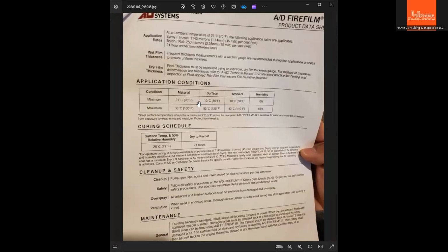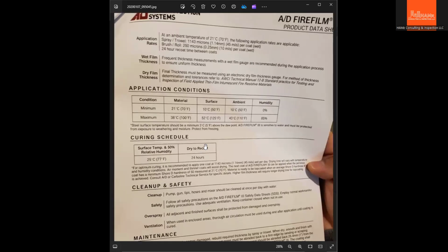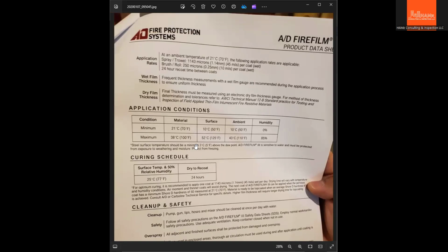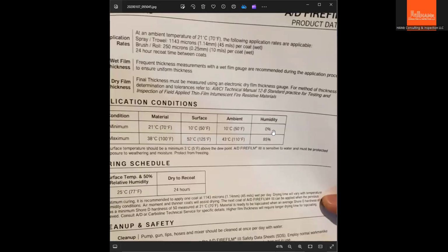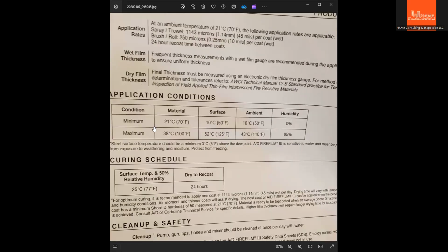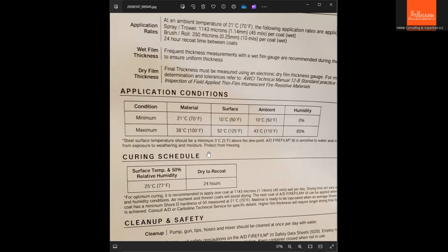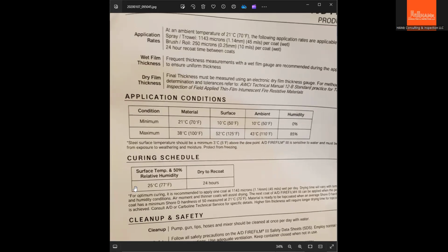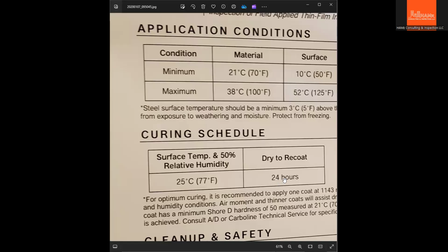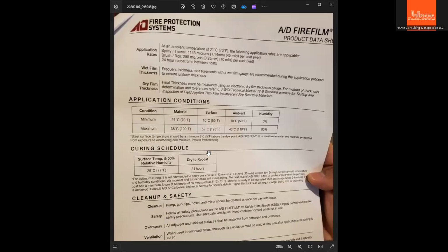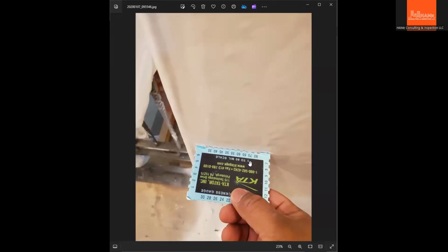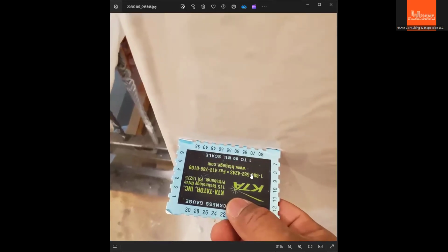And this is the application condition. This is one of the supporting documents, one of the pages for the fireproofing material, intumescent paint. So you're going to have 0 to 85 humidity, minimum to maximum, in the atmosphere or the room that you're doing it. So imagine you have 24 hours for another coating. So this is dry, 24 hours to wait for it to dry, to recoat. So it will take a long time. This is my own measuring of wet film thickness for reference record.